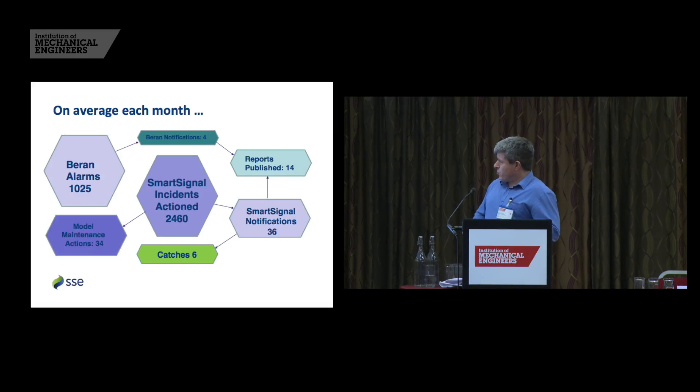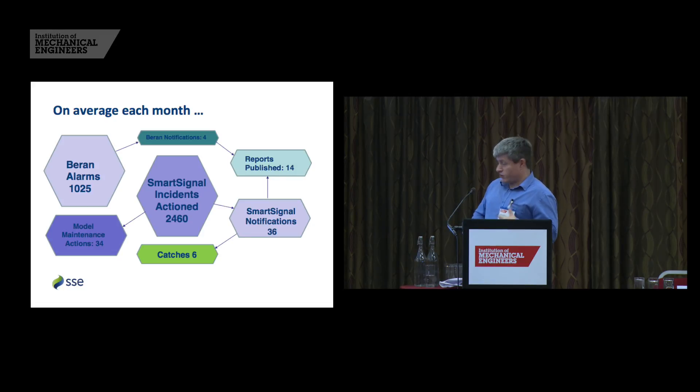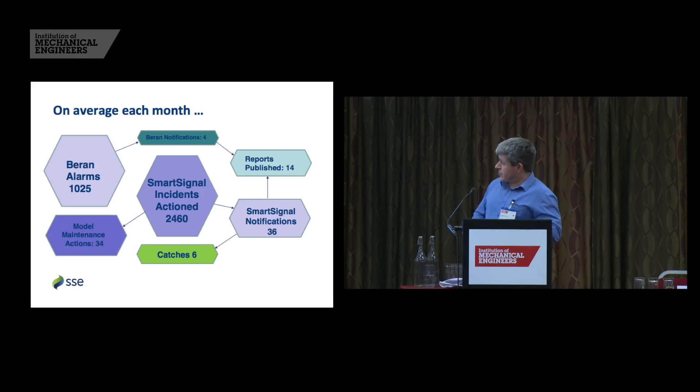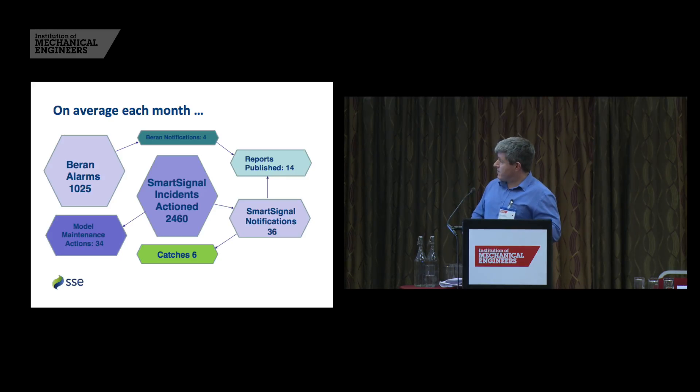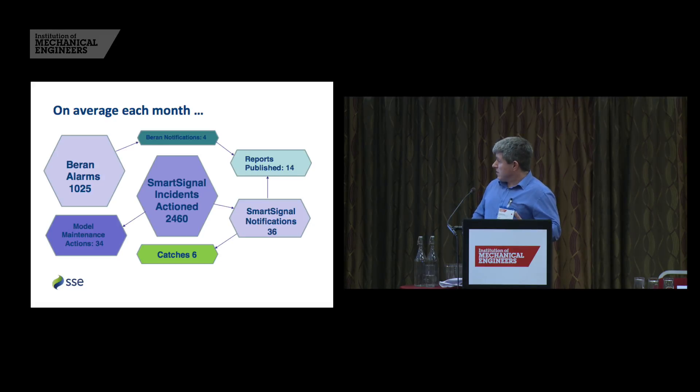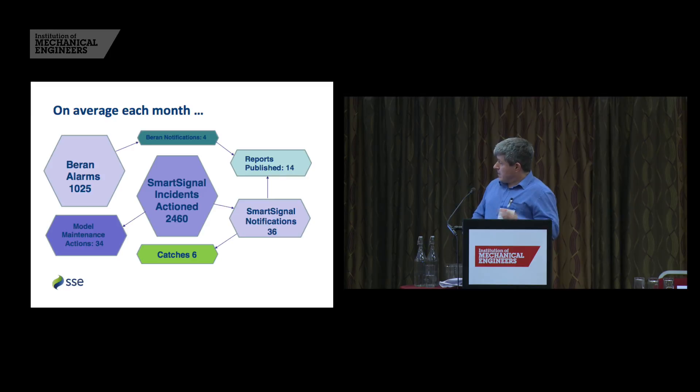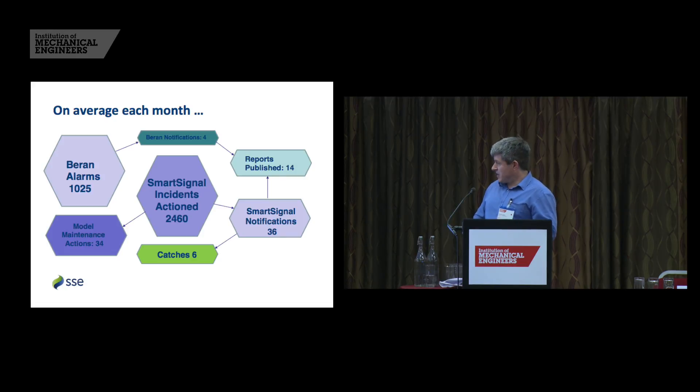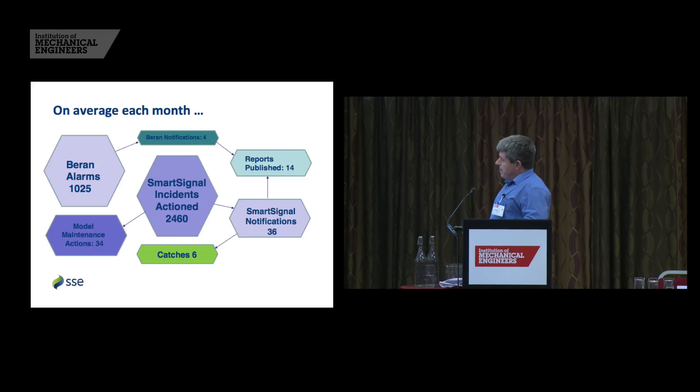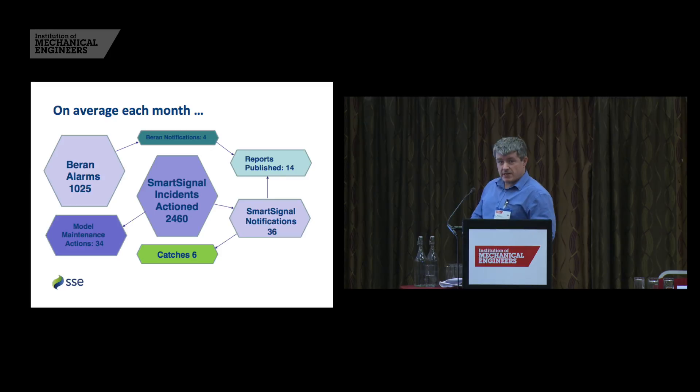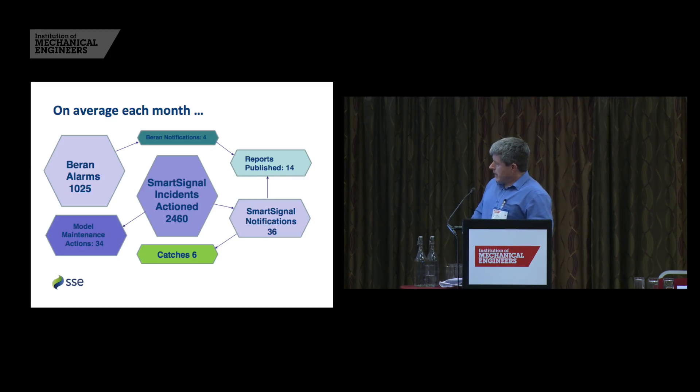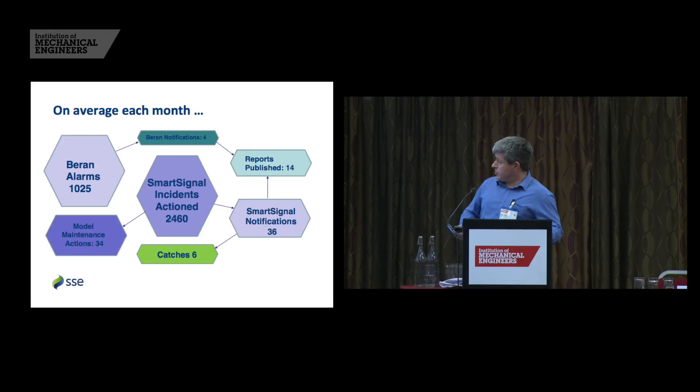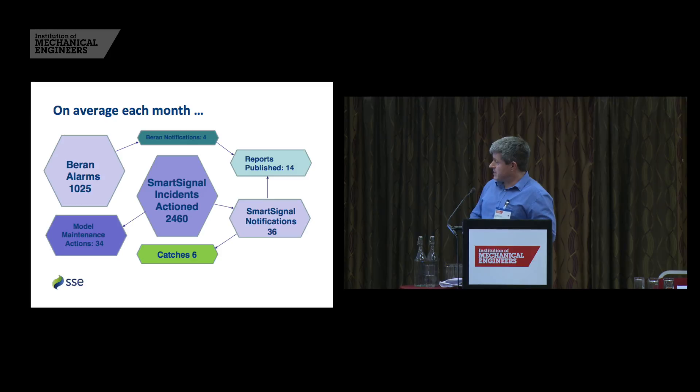So what does this mean in terms of workload? On average each month, with Beran, we also, Beran is a kind of sideshow in terms of this presentation because we're focusing on the Smart Signal. But we look at 1025 Beran alarms. We may be notified, send phone notifications to site about high vibration levels or other issues, oil well or something that they need to know about. Smart Signal incidents, we action 2,460. Remember when we've got 1,026 assets and a lot of those are wind turbines. We see a lot of incidents when the wind blows hard. From that 2,460, we send out 36 notifications to site to say you've got something that you probably need to look at. We might find that we have model maintenance to do to adjust for change in operating points, change in ambient condition. We probably do 34 asset maintenance actions or model maintenance actions during the course of a typical month.